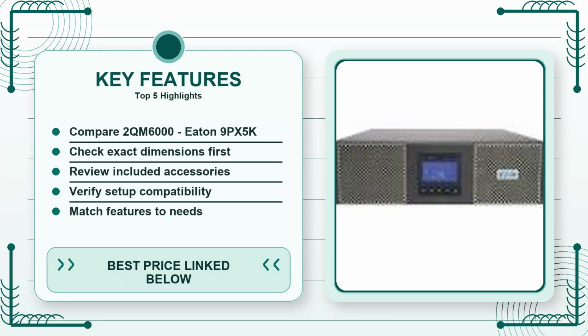Second, the input voltage range is fairly narrow, which means you need a fairly stable mains supply to avoid unnecessary trips. In regions with frequent voltage sags, you may need to install a voltage regulator in front of the UPS, which is another expense you hadn't planned for.